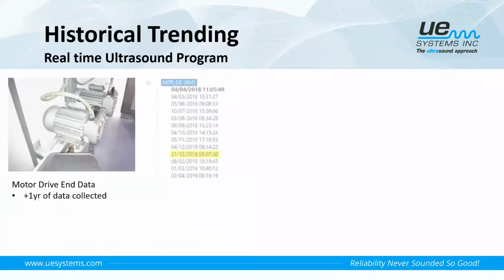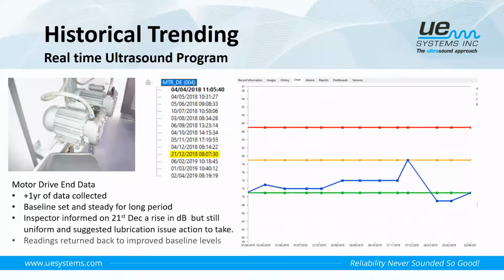With the same program, we had another motor drive end bearing being inspected on this site. We had another year's worth of data, where we can see a little yellow highlight, a low level alarm being indicated. The baselines were set, and as I said to you, when you have a good baseline, it will stay steady for a long period of time. But it started to climb slightly, and then all of a sudden we see an increase to 8 decibels above the baseline, which indicates a low level alarm and some lubrication may be required. The inspector on this site told me they discovered this low level alarm, and they did some rectification work. Afterwards, the reading has returned back to a low level again, and we're running nice and smoothly. Great way of using historical trending.